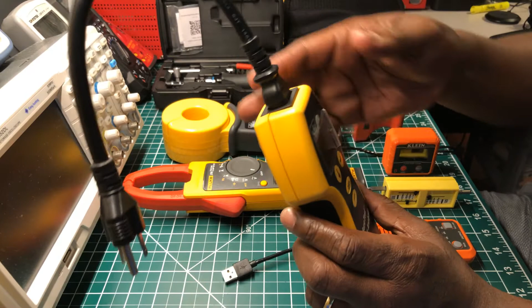After the installation is done, all the receptacles are in and the power is turned on, you want to go around to all your outlets and plug this in to make sure everything is wired correctly, and check for voltage drop and things like that. This circuit analyzer checks the circuit to make sure everything is up to code. I already did a review on this, so you can check that video.